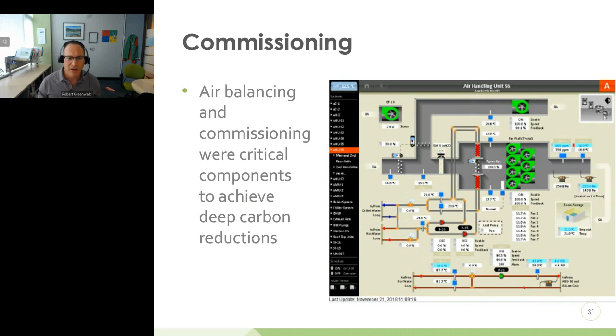Controls and commissioning were so critical, and air balancing was important. You can see in the schematic here, from the DDC system, those 7 fans, and the amount of tweaking we had to do, everything from finding leaky ducts because we weren't getting the air up to where we thought it would be, to tuning holistically to improve performance. It took 6 to 9 months to make it happen.